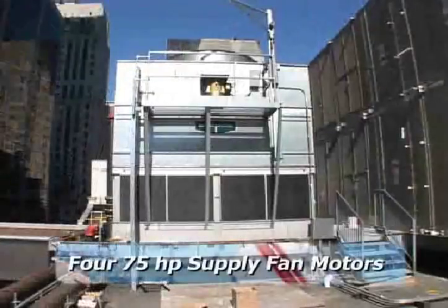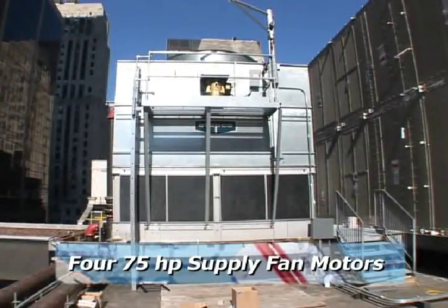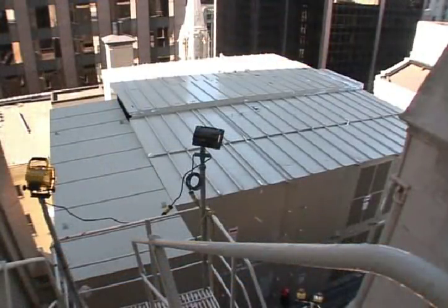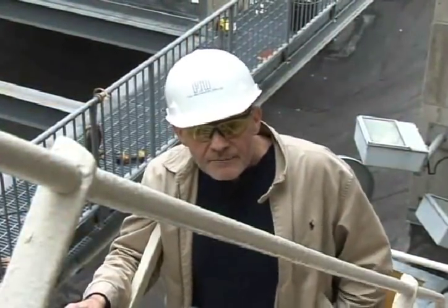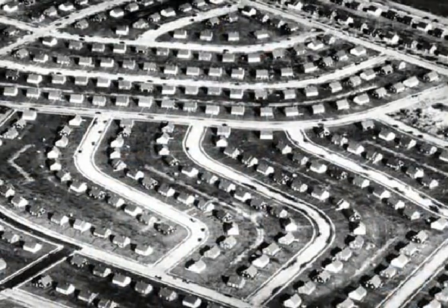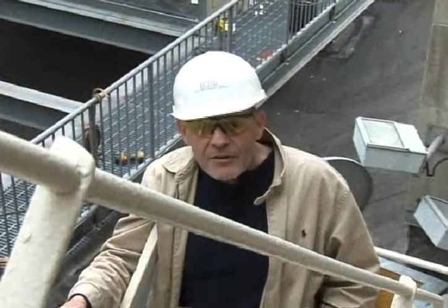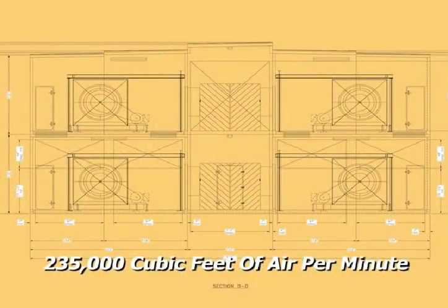There are four 75-horsepower supply fan motors and four 25-horsepower return fan motors. It'll handle about 900 tons of air conditioning. I suppose if you want to equate it to how much that is, that's enough to do about 300 average homes. So it has to have enough fan capacity to move 235,000 cubic feet of air per minute through the building for the heating, ventilating, and air conditioning.